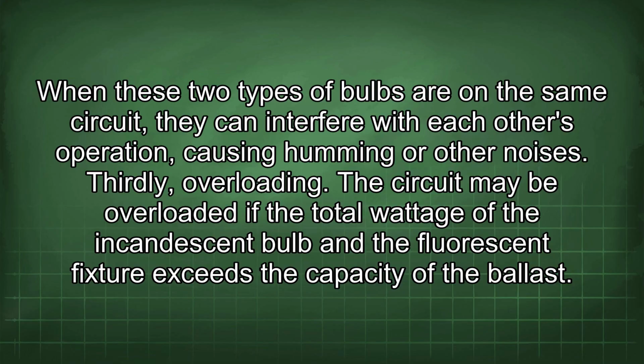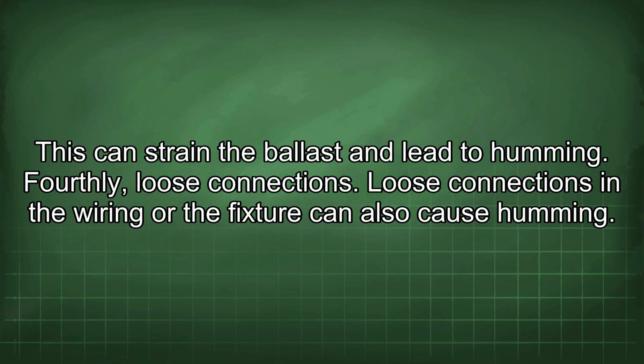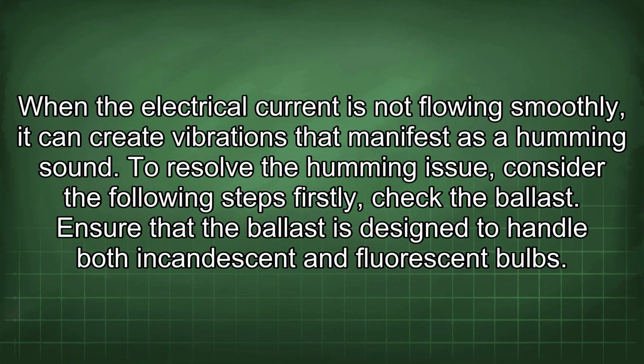The circuit may be overloaded if the total wattage of the incandescent bulb and the fluorescent fixture exceeds the capacity of the ballast. This can strain the ballast and lead to humming. Fourthly, loose connections. Loose connections in the wiring or the fixture can also cause humming. When the electrical current is not flowing smoothly, it can create vibrations that manifest as a humming sound.